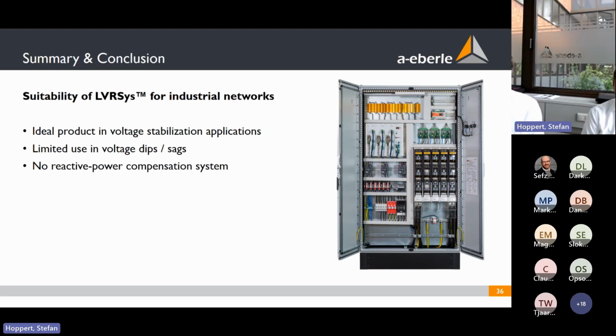I don't have them. THD level means the harmonic distortion. Our system makes no distortion, no harmonic effects, because we just switch the transformers on and off. So they have no harmonic distortion, but also the tap changer, I think, has no harmonic distortion. And yeah, you can add anything?